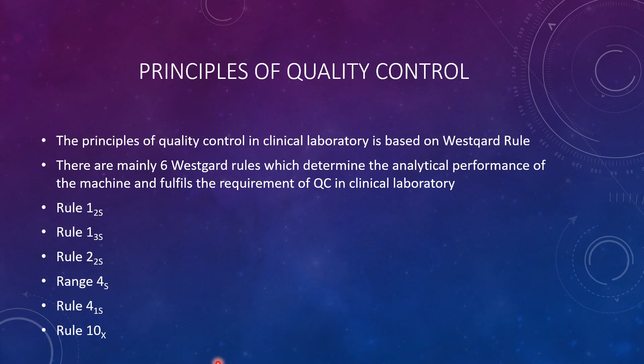Now if you look at the definition of quality control which we saw, it's a statistical process which monitors the analytical capability of the machine. So all the quality control we're dealing with is about the quality of the machine only, and Westgard rules also test the various analytical performance of the machine. So what are these rules? Rule 1 2s, 1 3s, 2 2s, R 4s, rule 4 1s, and rule 10x. There are 6 rules. Let us look at these rules one by one.